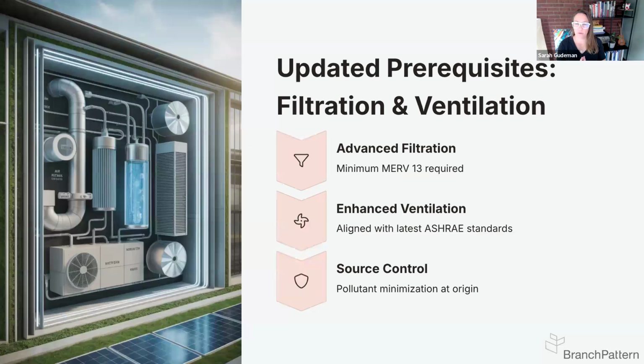And the MERV 13 requirement in central HVAC systems is to put filters in those systems that provide either outdoor air or recirculated air. So there's a lot of qualifications embedded in this sentence, but it's outdoor air and/or recirculated air to regularly occupied spaces.